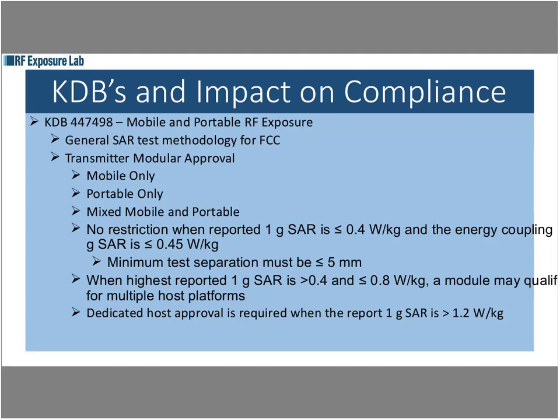The first thing you have to do, if you're going to do a transmitter modular approval, is determine how that module is going to be used. You can be mobile only, portable only, or mixed mobile and portable. Any module manufacturer going through SAR testing really should have their modules approved for mixed mobile and portable. It makes it much easier as you go through the process and do any type of Class 2 permissive changes, because it will keep the whole file operating, since you can have both types of devices within the same filing.